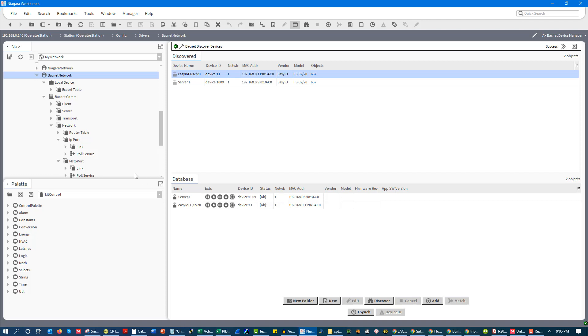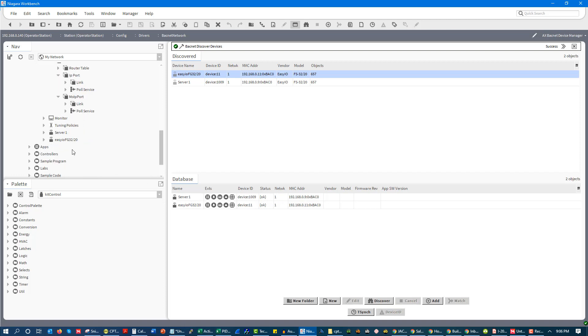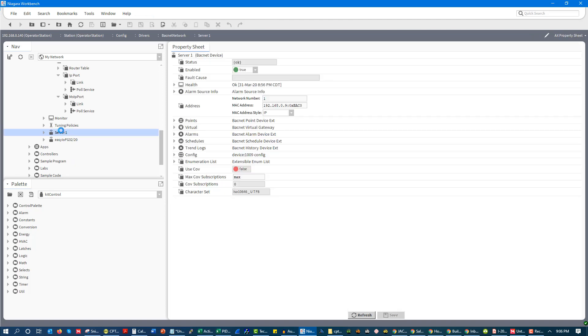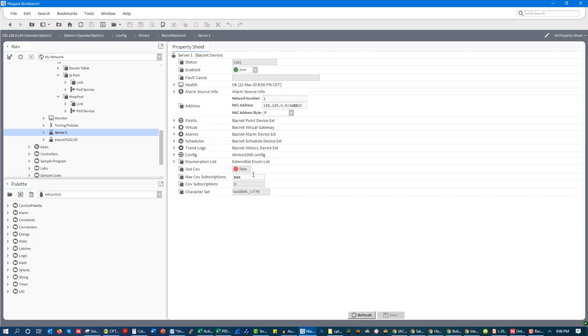So we'll go into server 1, and we'll see. It's all communicating. Everything's all good. So if we scroll down, we'll see server 1 down here. And now we can see a lot more data now that the controller is mapped in. We can see our network number, our address. We can see that we have BACnet alarms, any BACnet schedules, any BACnet trend logs. If we were going to use change of value, we could do that. More on that later when we talk about trends and extensions like that.